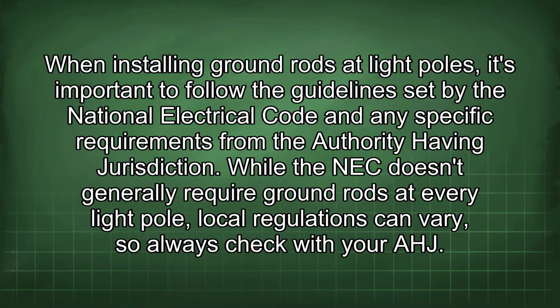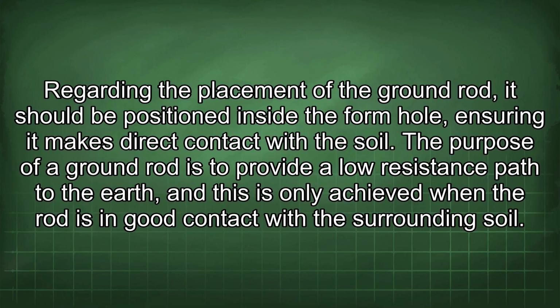When installing ground rods at light poles, it's important to follow the guidelines set by the National Electrical Code and any specific requirements from the authority having jurisdiction. While the NEC doesn't generally require ground rods at every light pole, local regulations can vary, so always check with your AHJ. Regarding the placement of the ground rod, it should be positioned inside the form hole, ensuring it makes direct contact with the soil.